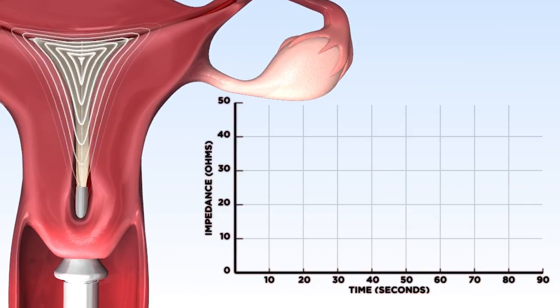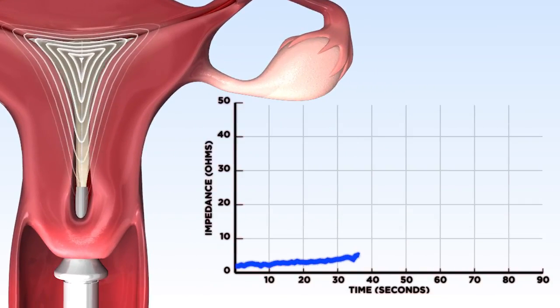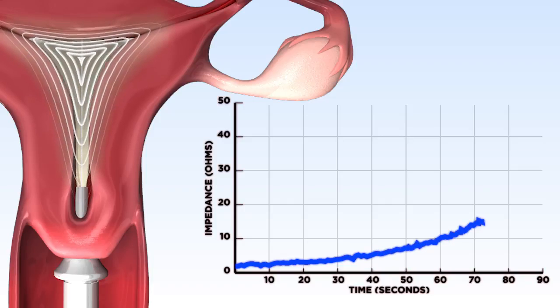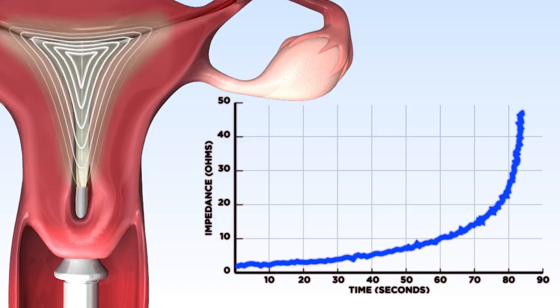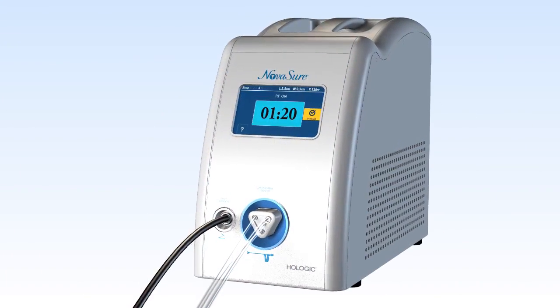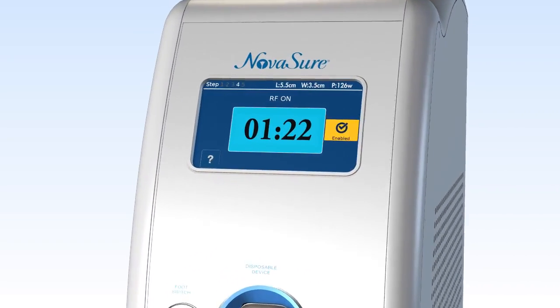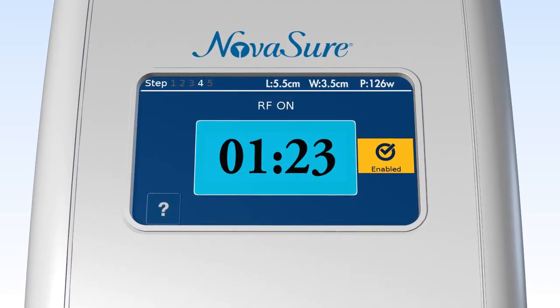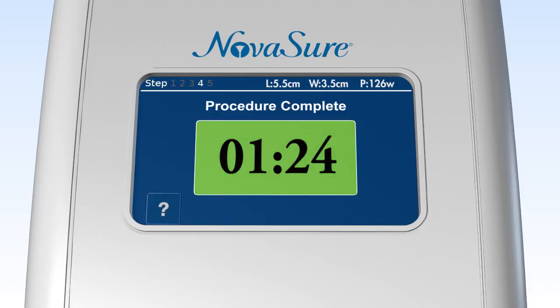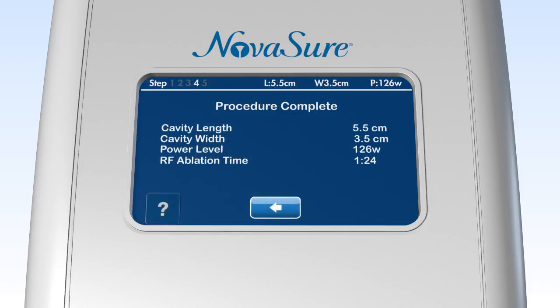The radiofrequency energy desiccates the endometrium, and the procedure self-terminates once tissue impedance reaches 50 ohms of impedance or when the treatment timer reaches 2 minutes. The controller has an ablation timer which monitors procedure duration. The procedure is complete after 120 seconds or when the endometrium reaches an impedance of 50 ohms, whichever is achieved first. The Procedure Complete screen displays the following information at the end of each NovaSure procedure: cavity length, cavity width, power level, and RF ablation time.